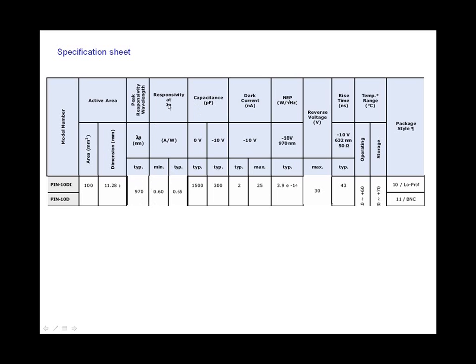Responsivity has the same units as sensitivity. It's just amps per centimeter squared over watts per centimeter squared to give you amps per watts. Usually, responsivity curves are normalized to the peak wavelength. The capacitance is the internal capacitance, and you need to know this because this dictates the speed of the photodiode and the RC time constant.